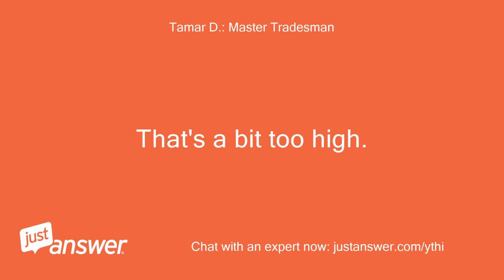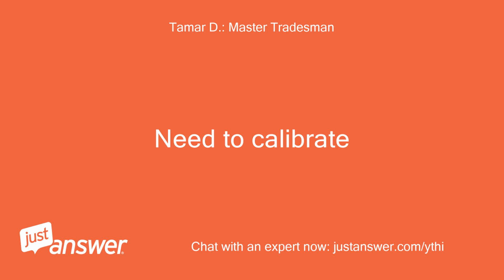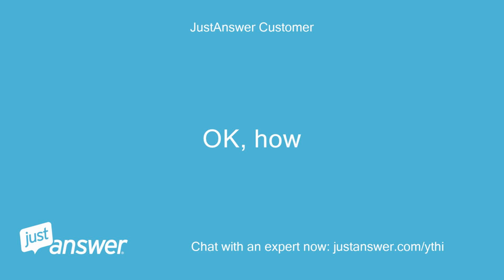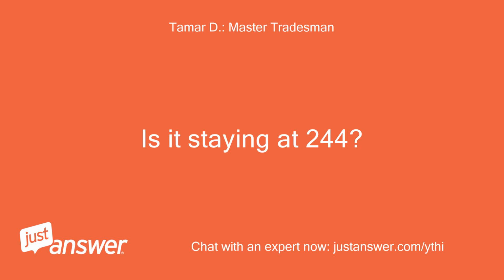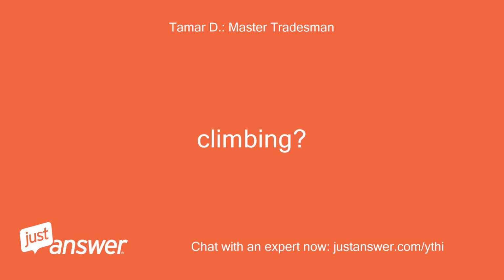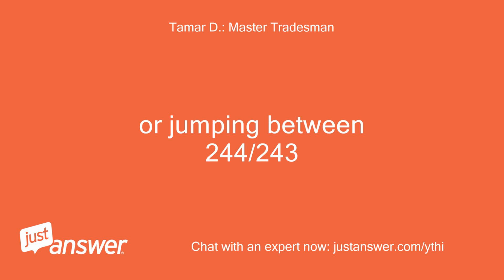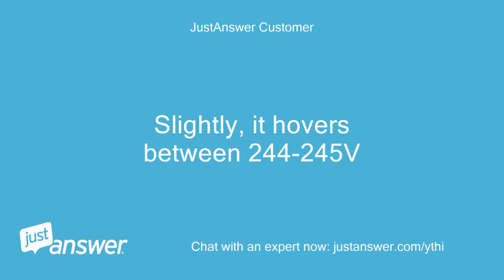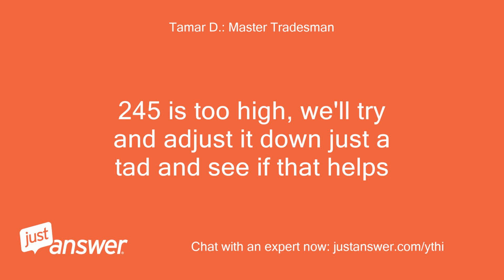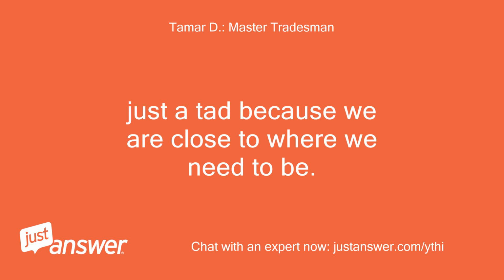That's a bit too high. Need to calibrate. Okay, how? Is it staying at 244? Climbing? Or jumping between 244 and 243? Slightly, it hovers between 244 to 245 volts. 245 is too high. We'll try to adjust it down just a tad and see if that helps. Just a tad because we are close to where we need to be.